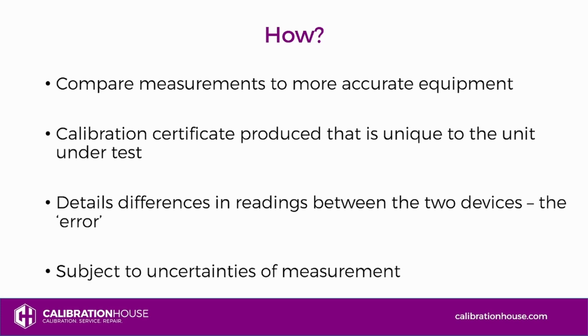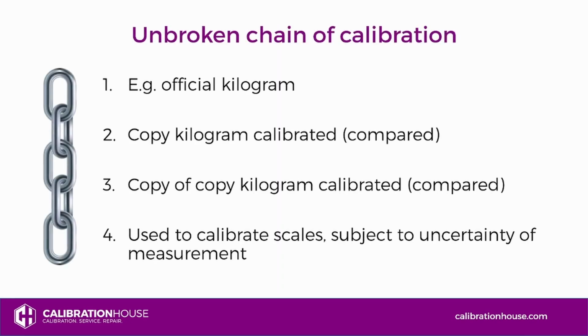So how does calibration work? You compare measurements for the instrument under test to more accurate equipment. A calibration certificate is produced that is unique to the unit under test. This certificate details the differences in readings between the two devices, which is known as the error. And this is subject to the uncertainties of measurement. There is an unbroken chain of calibration that leads back to a national or international standard.